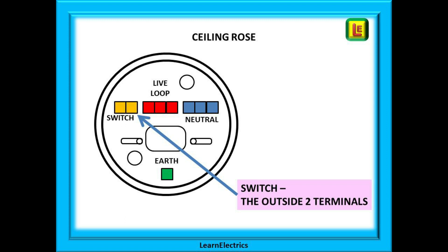The outside block of two, colored yellow here, is called the switch block. The middle block, colored red, is known as the live loop or just loop. And finally, the outside block of three, colored blue, is always neutral. Always follow this sequence.